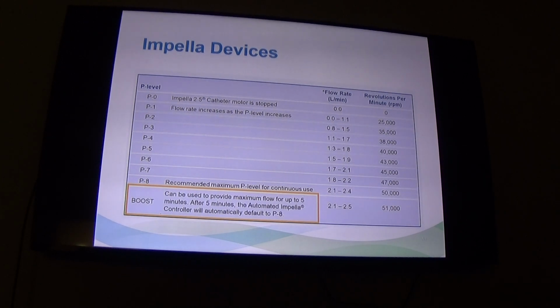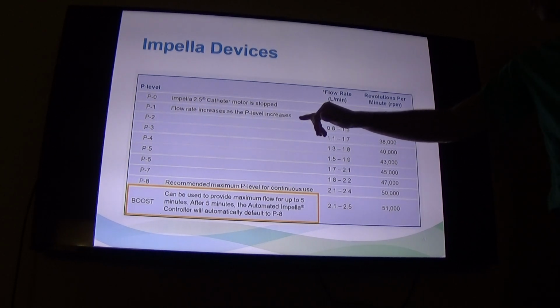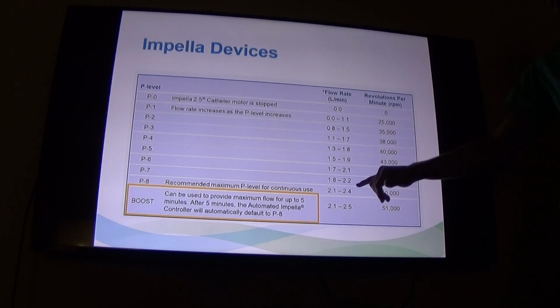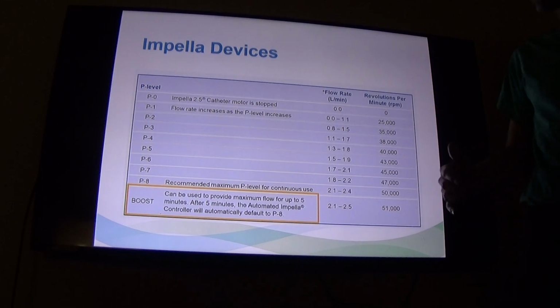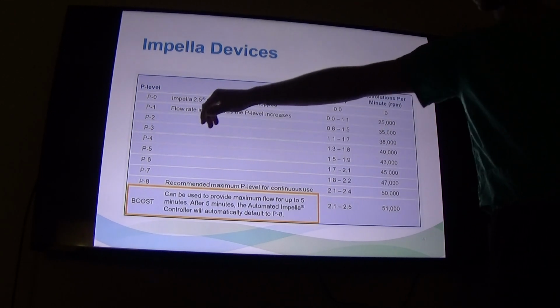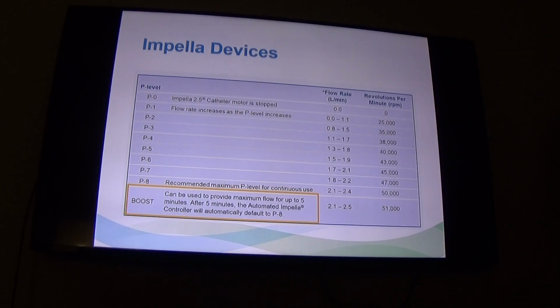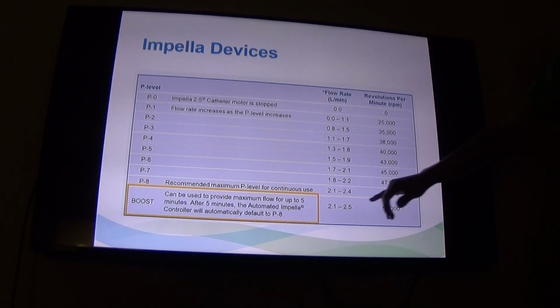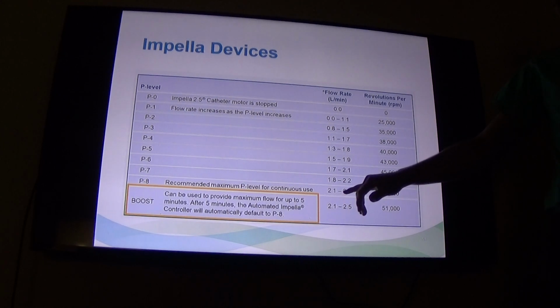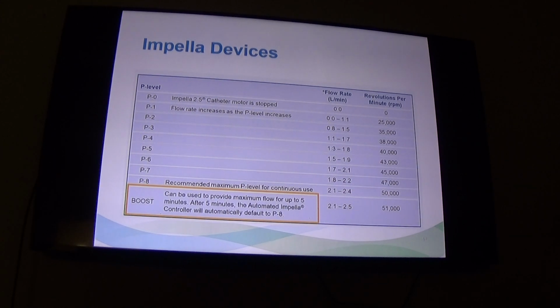So if you come in, you see a patient on the ICU or wherever, and they are having a P level that's, you know, very different from the flow rate. So perfect example, the last transport I did, person was at a P1, which really is only used for insertion and removal, but their flow rate was like 3 on a CP, which is pretty high. I was like, there's something wrong. We went to the placement screen, we identified that it wasn't across the aortic valve, so it had to be adjusted.